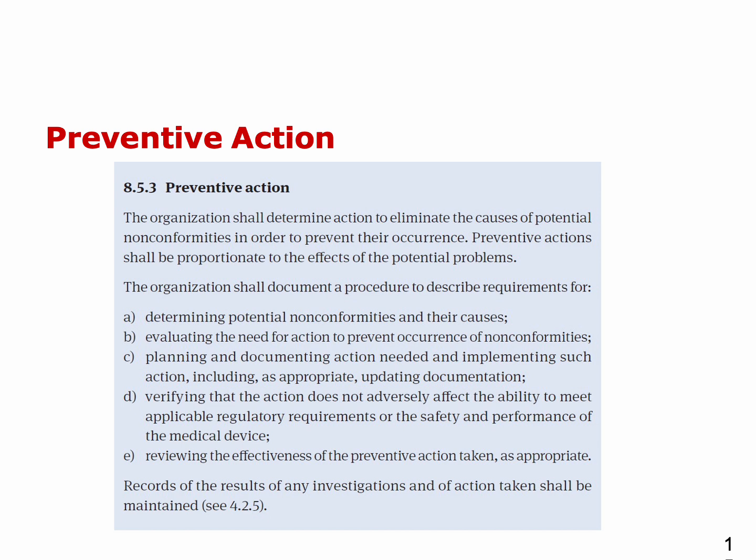So point A, determining potential non-conformities and their causes. Point B, evaluating the need for action to prevent occurrence of non-conformities. Point C, planning and documenting action needed and implementing such actions. Point D, verifying that the action doesn't adversely affect the ability to meet applicable regulatory requirements or the safety and performance of the medical device.